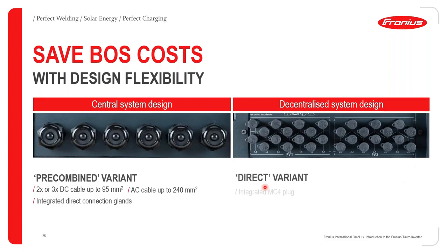As far as the cable cross sections for the AC side, that will remain the same, regardless of whether you've ordered a direct or a pre-combined version. What is important to note here is that the cable glands that you require for the DC connection area for the centralized or the pre-combined version will come integrated into the inverter. So you don't need to worry about looking for appropriate cable glands.